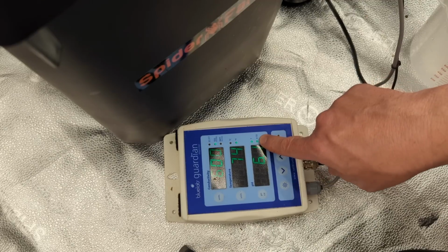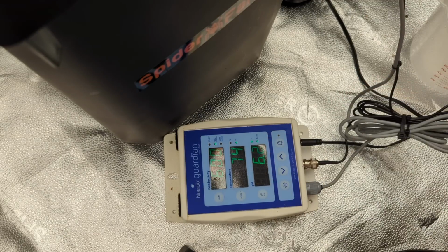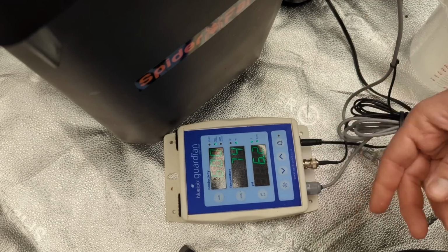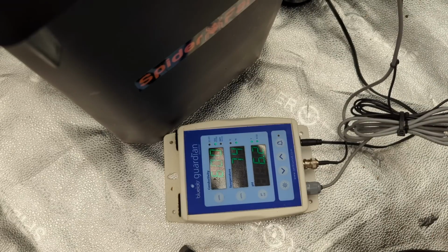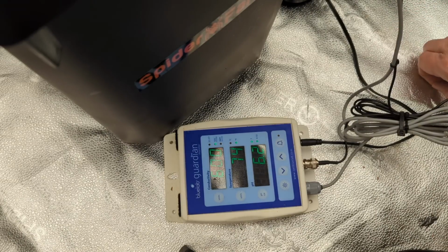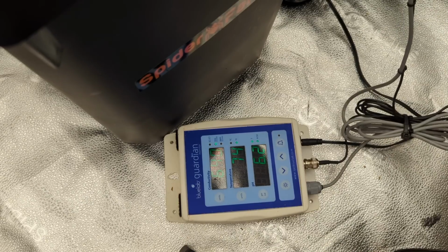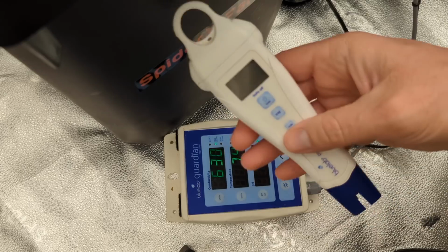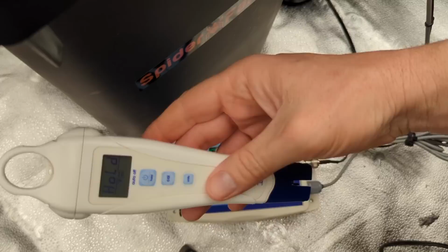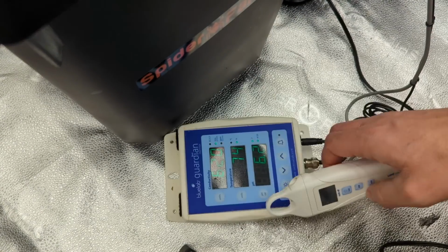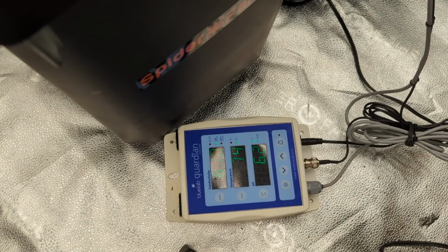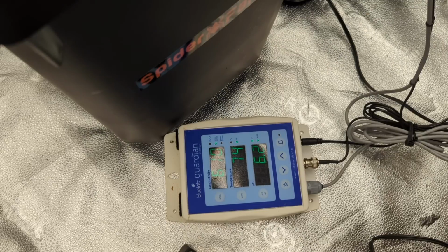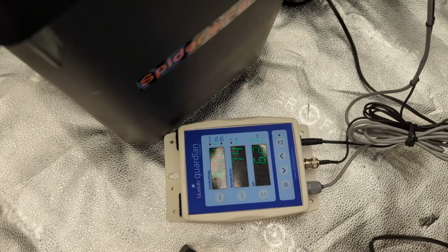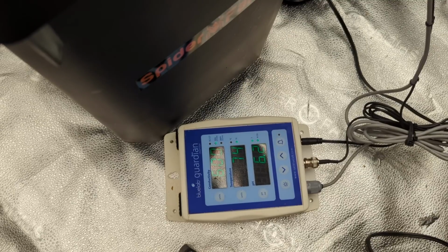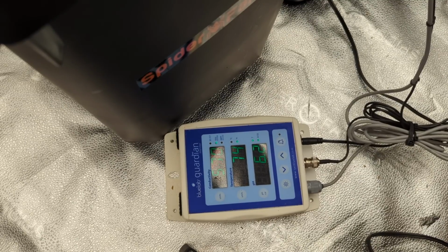When they're flashing, they're not telling you that the meter is not accurate or there's something wrong with it. They're flashing because it has an internal timer that starts flashing every 30 days, just reminding you that it should be calibration time. So it says we're at 640. Let's cross-reference that with a handheld unit here. On hold, it says we're at 650, and this is saying 620, so we're 30 ppm off. That's not going to be detrimental to the plants at all. If we were a couple hundred ppm off, I would be concerned, if it was anything more than 100 or 200. I just wanted to clear up any of your questions in the comment sections.